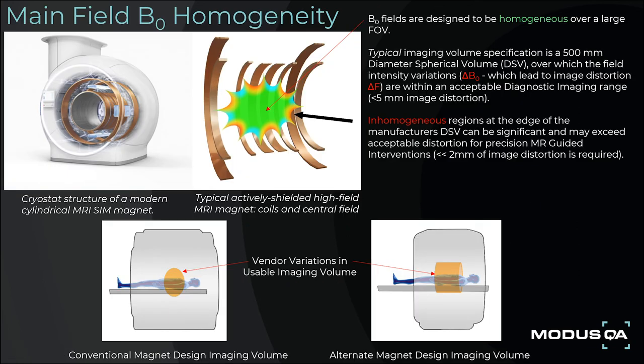All main field magnets for MRI generate strong B0 magnetic fields, designed to be homogeneous or of uniform intensity over a large volume. The typical size of the imaging volume is a 500 mm diameter spherical volume, or DSV, over which the field intensity variations — B0 inhomogeneity — which lead to image distortion, are within an acceptable diagnostic imaging range, typically less than 5 mm of image distortion. Inhomogeneous regions at the edge of the manufacturer's DSV can be significant, and may exceed acceptable distortion for precision MR-guided interventions, where less than 2 mm of image distortion is desired.